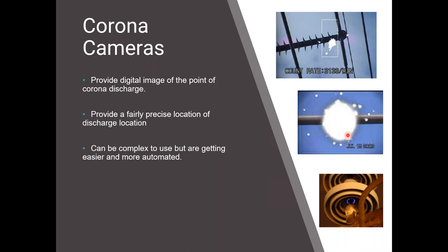They frequently have some level of amplitude, but one of the drawbacks is you do need a line of sight. If you've got a barrier board or a door, you're not going to be able to pick it up. Okay. So going into medium voltage switchgear, you're going to have to open doors up. It can help identify it if you see corona on it, another test, but typically it's more for overhead, or if you can't open doors, you can scan around in a cubicle and see where the partial discharges are happening. You'll see large clusters of light like this in those areas.